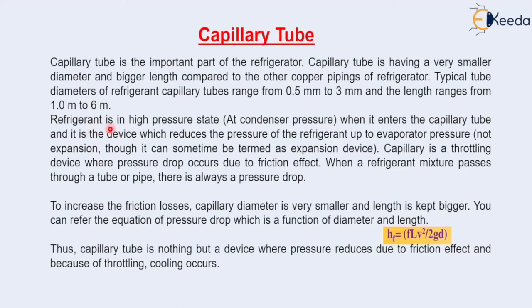Refrigerant is in a high pressure state — at condenser pressure — when it enters the capillary tube. The capillary tube reduces the pressure from condenser pressure to evaporator pressure. It is actually not an expansion device; though it can sometimes be termed as one, it is actually a throttling device, because for the capillary tube the process is isenthalpic — enthalpy is constant — and pressure drop occurs due to friction effect.